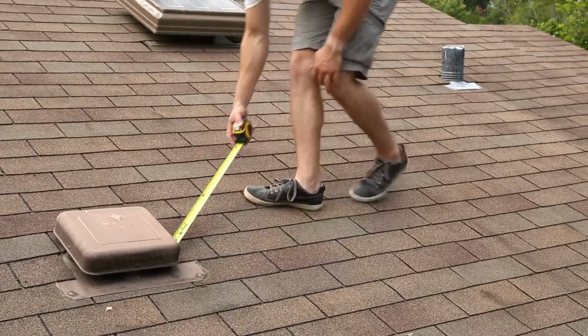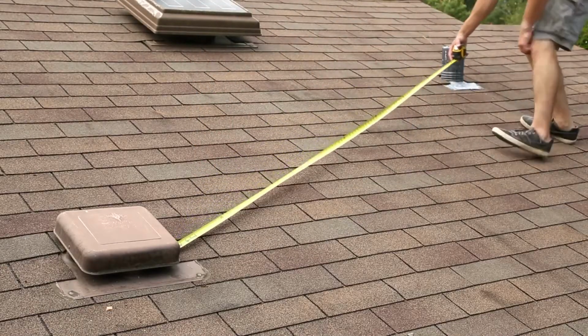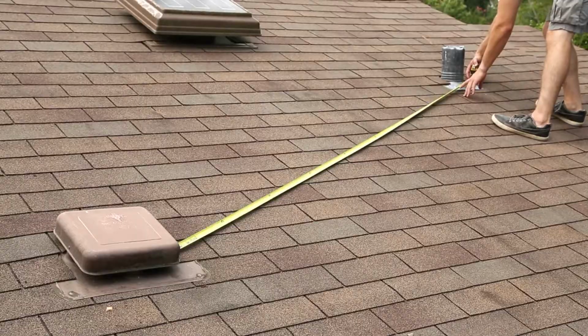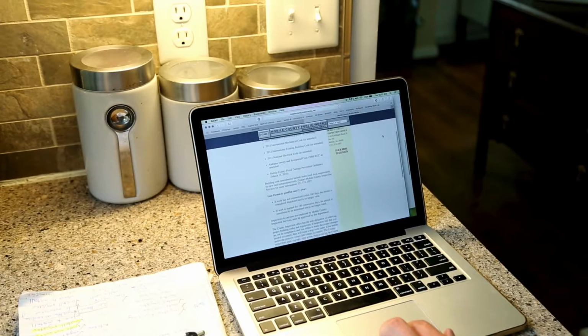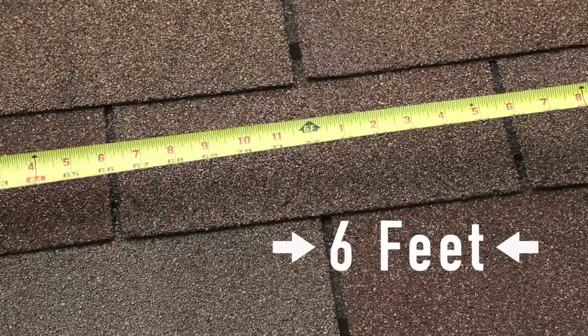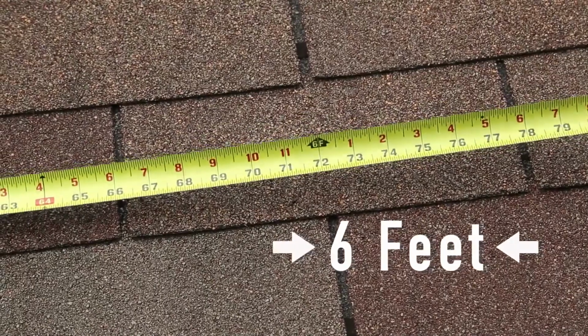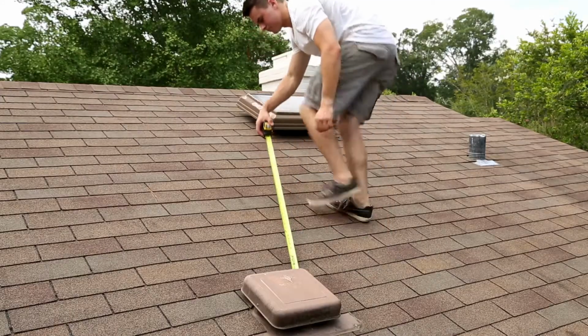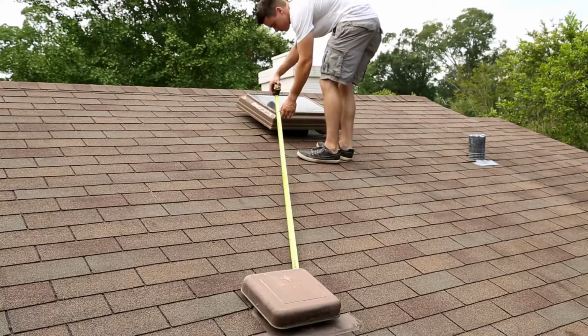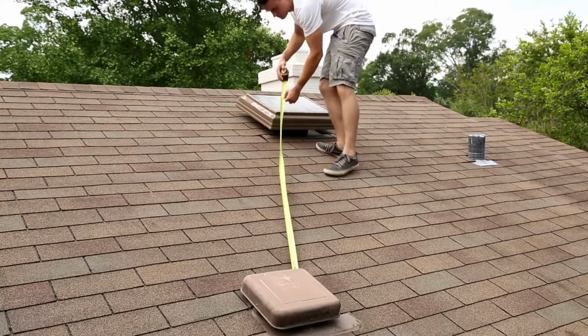Now it is time to install the stale air exhaust hood and fresh air distribution hood. Consult applicable building codes to determine hood placement. To avoid contamination, ensure the intake hood is at least 6 feet from any exhaust. You also want at least 6 feet between the exhaust and distribution hoods to avoid contamination.